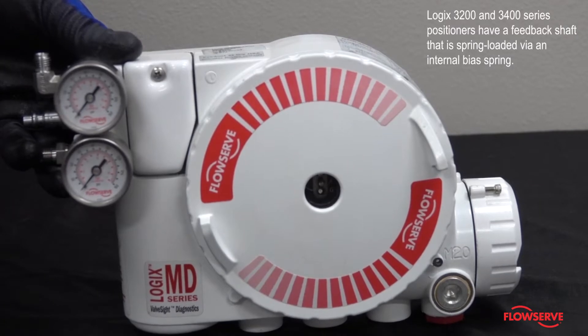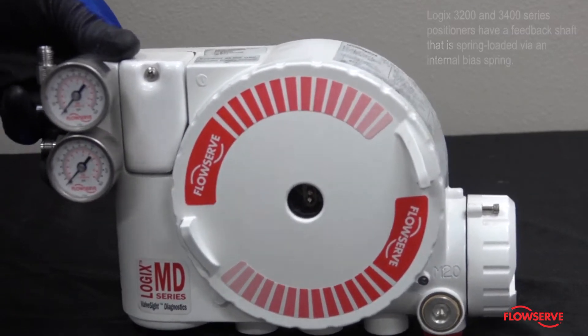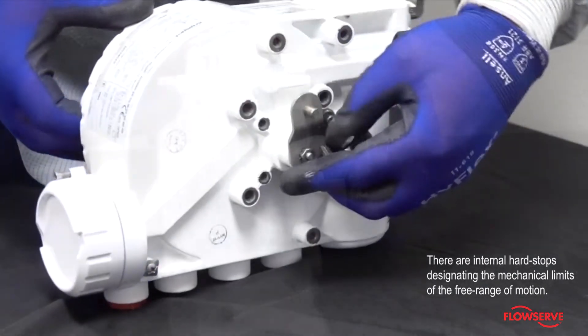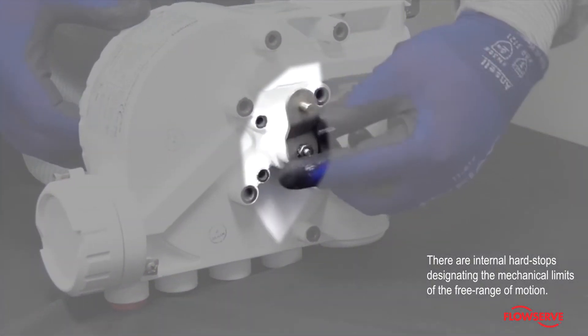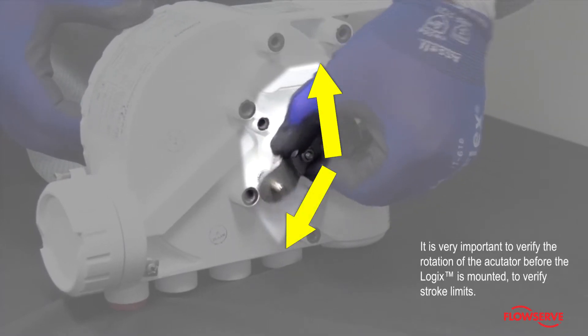Logix 3200 and 3400 series positioners have a feedback shaft that is spring-loaded via an internal bias spring. There are internal hard stops designating the mechanical limits of the free range of motion. It is very important to verify the rotation of the actuator before the Logix is mounted, to verify stroke limits.